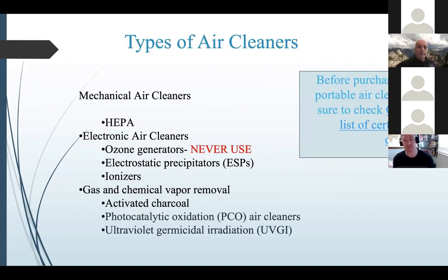There are multiple types of air cleaners out there. The ones we're getting a lot of pushback on are the ozone generating filters. If those aren't watched carefully and you have poor ventilation, you're actually increasing the ozone to dangerous levels in your space. So you have to be careful with ozone generators as a means to combat COVID, because if not watched carefully, they can be more problematic and cause more issues than they help. I'd discourage anybody from using them - instead invest your resources into good ventilation and good mechanical operating systems.